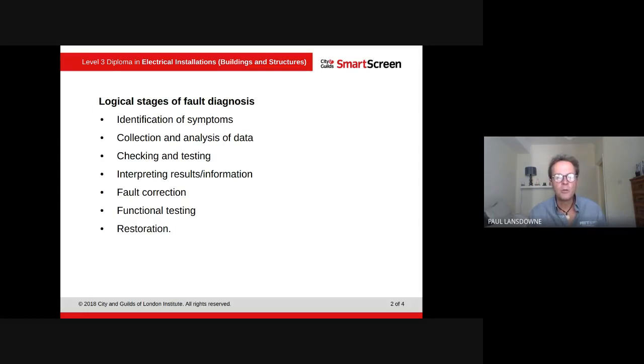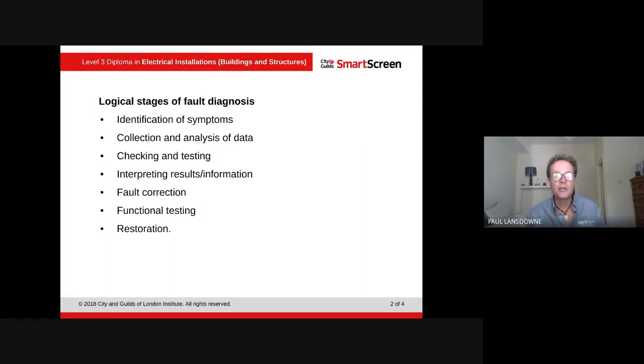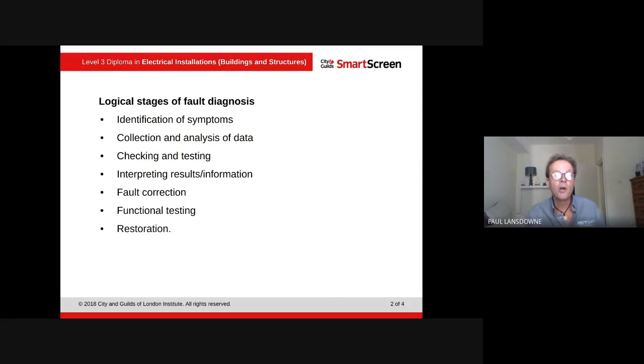In the check and test phase, if we put a tester on something and did an insulation resistance test and were expecting a very high reading but got a very low reading — almost indicating a short circuit — we'd know we had a short. Or we'd do a continuity test, maybe on a lighting circuit, and see that we had no continuity on a line conductor going from the circuit board to the light.